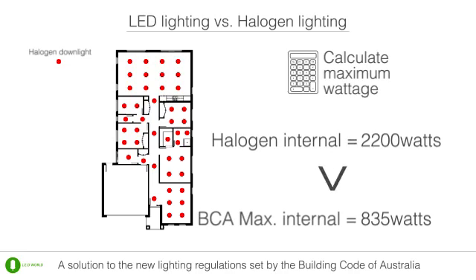Since 2,200 watts is greater than 835 watts, the example house does not meet the new BCA regulations. The best solution to this problem is to use LED downlights. For this house, LED downlights can be used in the exact same arrangement as halogen downlights.